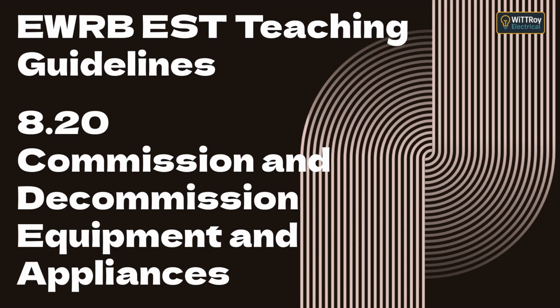1. Continuity of the earth, less than 1 ohm. 2. Insulation resistance, greater than 1 megohm. 3. Polarity, switch and fuse in the active. You refit all covers and briefly energize to check rotation. The motor runs smoothly and safely. You record the results and remove your tag. That's a safe and fully compliant reconnection.